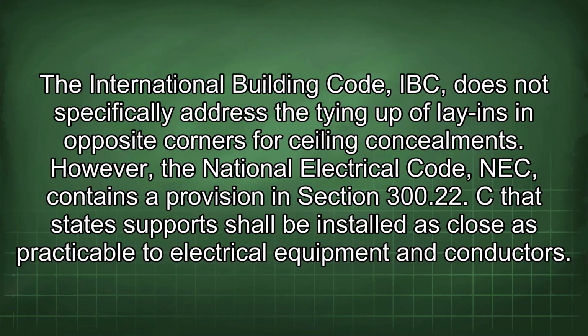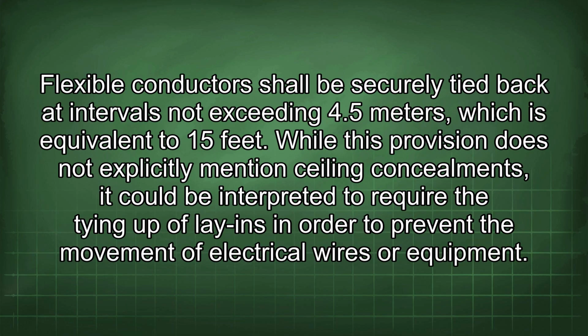The International Building Code (IBC) does not specifically address the tying up of lay-ins in opposite corners for ceiling concealments. However, the National Electrical Code (NEC) contains a provision in Section 300.22(C) that states support shall be installed as close as practicable to electrical equipment and conductors. Flexible conductors shall be securely tied back at intervals not exceeding 4.5 meters, which is equivalent to 15 feet. While this provision does not explicitly mention ceiling concealments, it could be interpreted to require the tying up of lay-ins in order to prevent the movement of electrical wires or equipment.